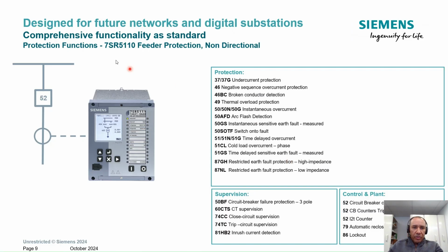In terms of protection functions, we start with the 7SR5110. This is a feeder relay. This device brings just CT, that means it's a non-directional relay. And these are all the protection functions that you can achieve using just the CT as input. Okay, special mention of the restricted earth fault for low impedance and high impedance. That's possible on this device.